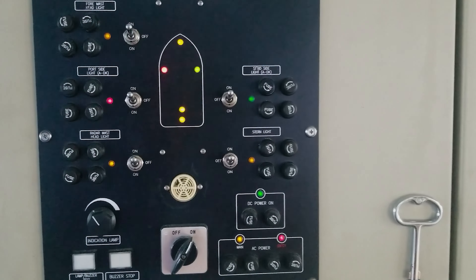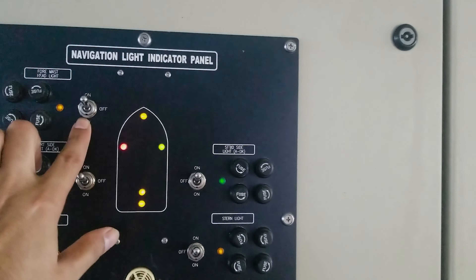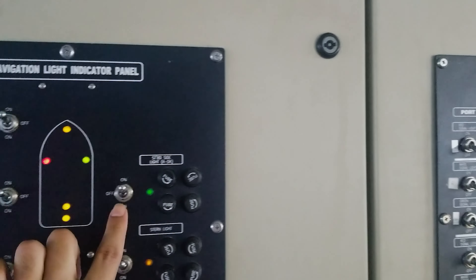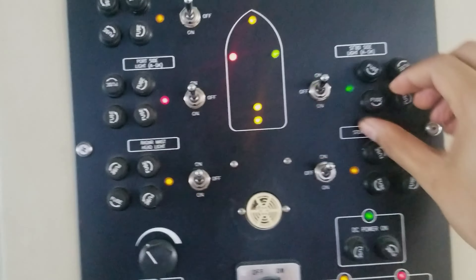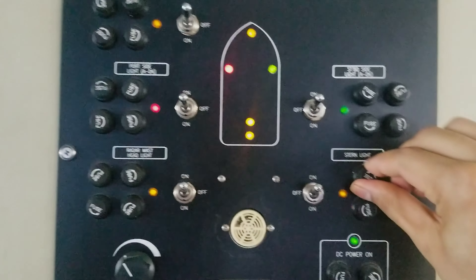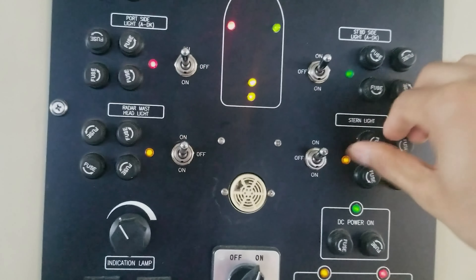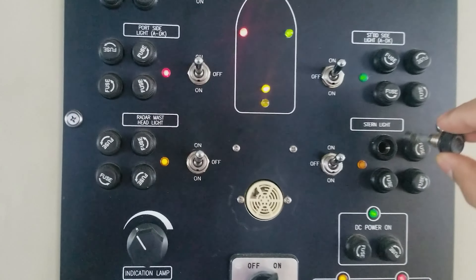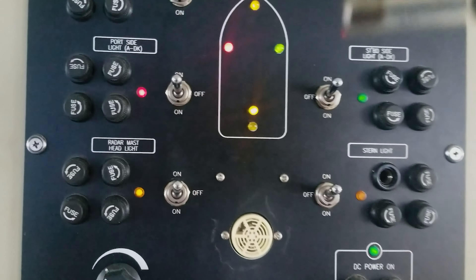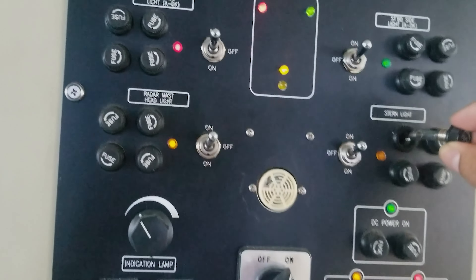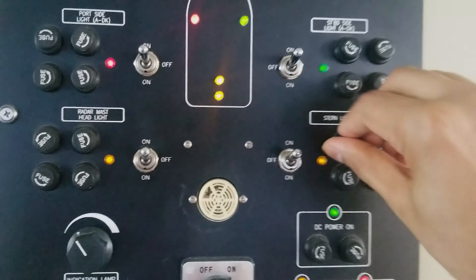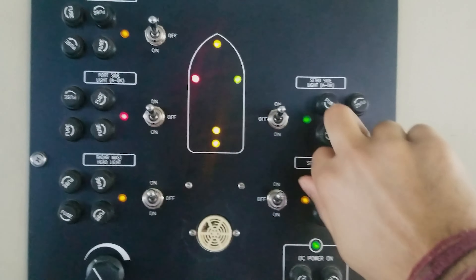For additional knowledge, I'll show you a different navigation light indicator panel. Here also, all navigation lights are switched on and upper navigation lights are selected. Unlike the previous panel where fuses were located below, on this panel the fuses are provided on the side of the panel. To perform the fuse test here, you simply turn the fuse anti-clockwise and remove it. You can hear the alarm sound. When you put the fuse back, the alarm is gone.